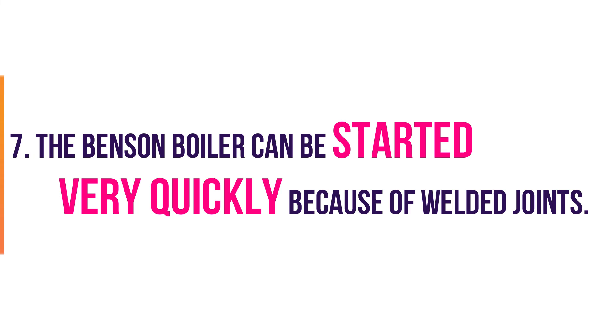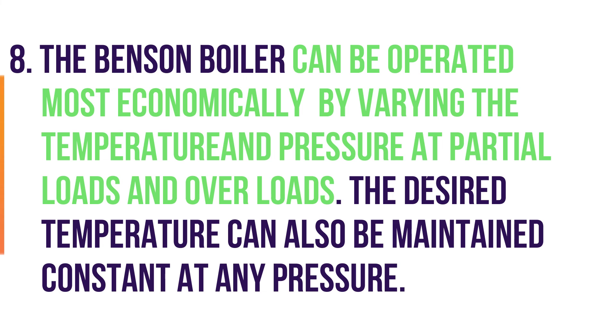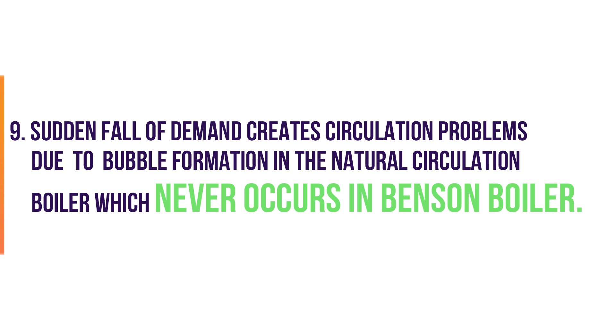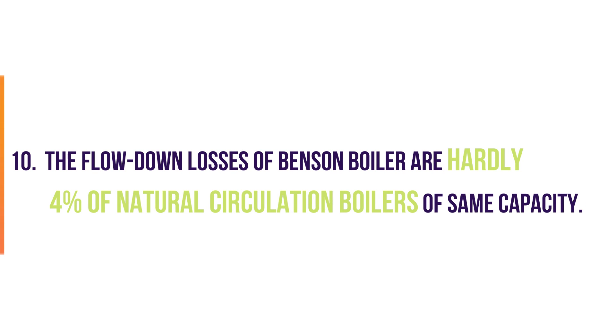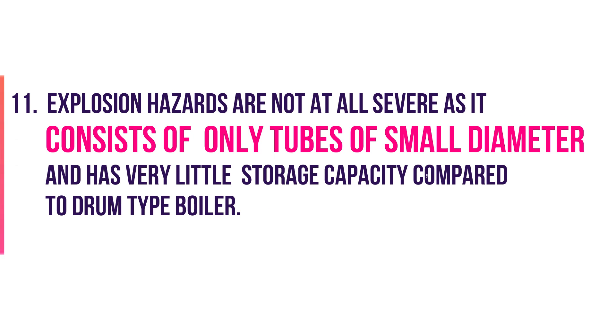The Benson boiler can be started very quickly because of welded joints and the absence of a drum. It can be operated most economically by varying temperature and pressure at partial loads and overloads, and the desired temperature can be maintained constant at any pressure. Sudden fall in demand creates circulation problems due to bubble formation in natural circulation boilers, which never occurs in the Benson boiler. Flow losses in the Benson boiler are only about 4% of those in natural circulation boilers of the same capacity.